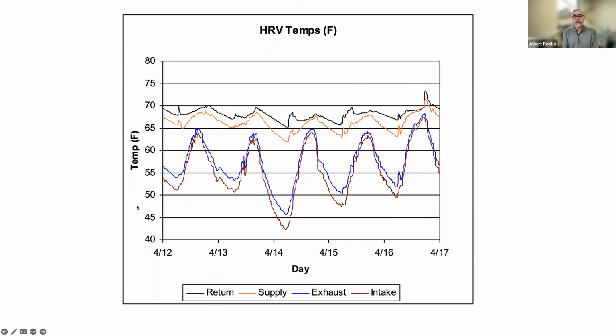So it's spring, and in this building, the heat has not been turned on yet. So this is just totally operating by the HRV and whatever warmth it gets from the sun and the occupants in the building. So you can see that the temperature on the 14th drops down to 42 or 43 degrees outside, but inside the building, the temperatures stay above, 63 is maybe the coldest the supply flow gets. The building doesn't get any colder than 65 or 66 because that's that black line at the top. So these things really work, and we can have a steady constant airflow of 100 or 120 CFM, which is probably about where this building is, without the building getting cold overnight when these temperatures dip.